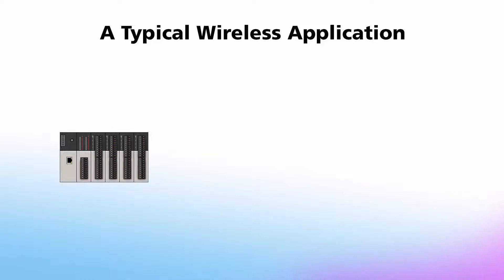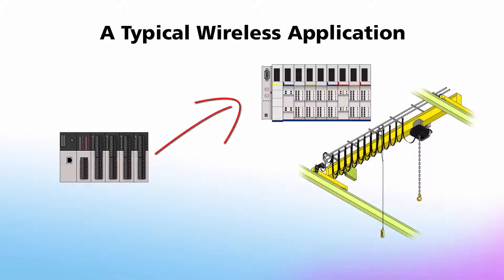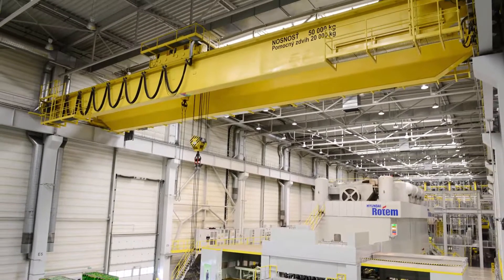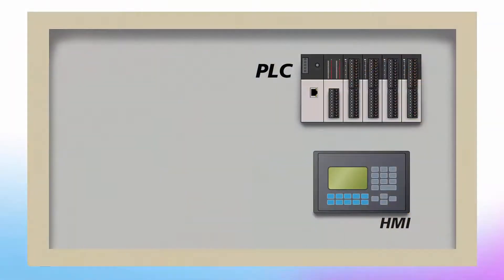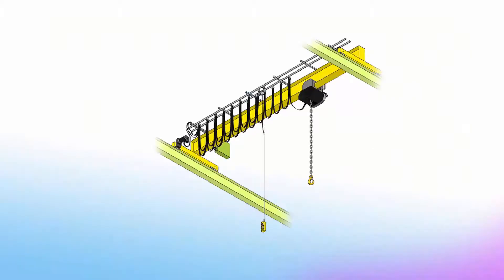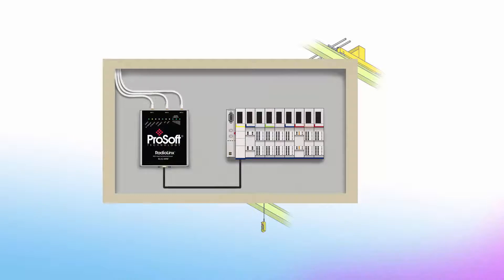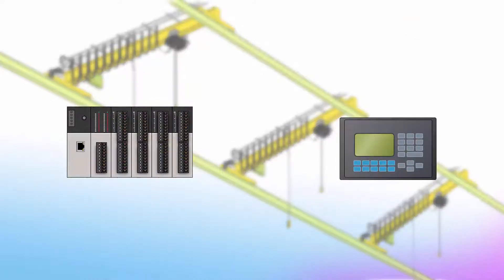Now, let's walk through a wireless application where you have a PLC that needs to talk to distributed I/O on an overhead crane — it could also be a rotating machine or other moving piece of equipment. In our example, your PLC is located in a control cabinet stationed on the factory floor. The control panel contains an operator terminal and the master radio connected through an Ethernet switch. Another control cabinet is mounted on the crane. It contains the other radio, set to remote mode, as well as the distributed I/O system which is connected to the crane motors and sensors. If your application has three of these cranes and you want to control them all from the PLC and the HMI, you would first need to determine how many I/O connections they have in each distributed I/O adapter and the update time of each connection.